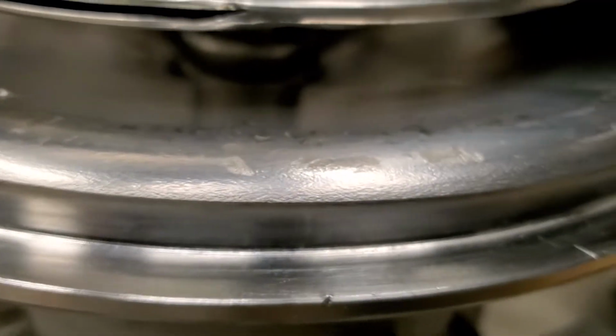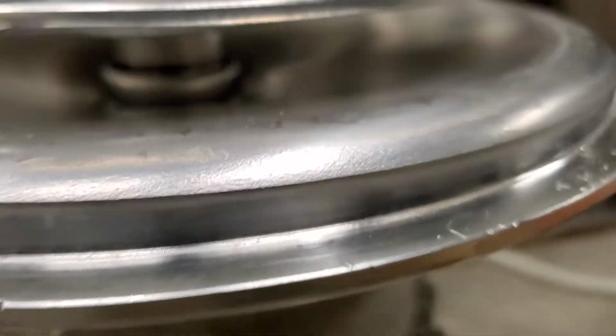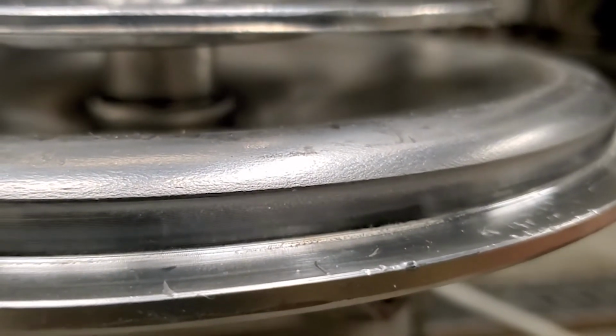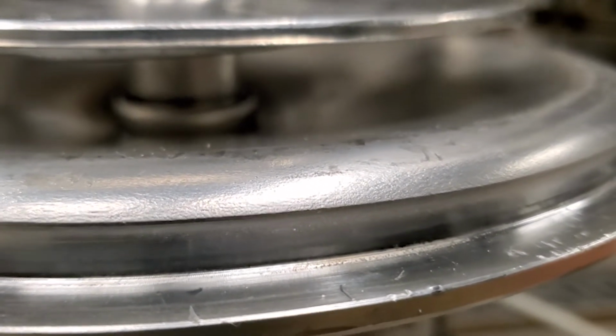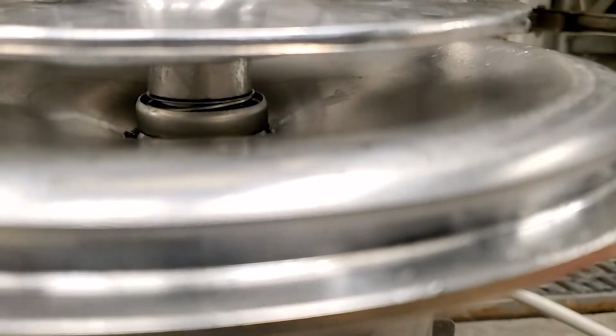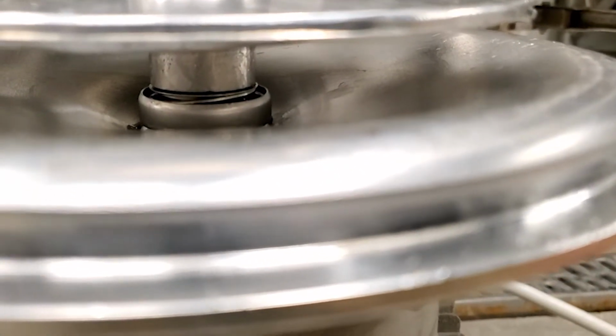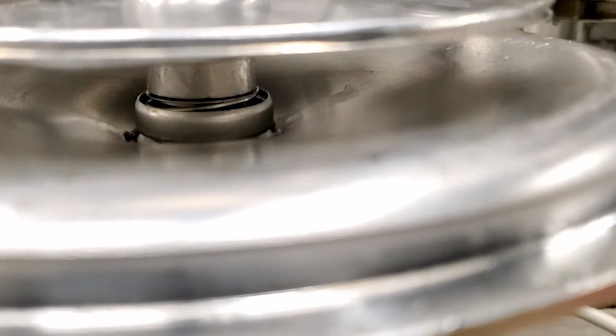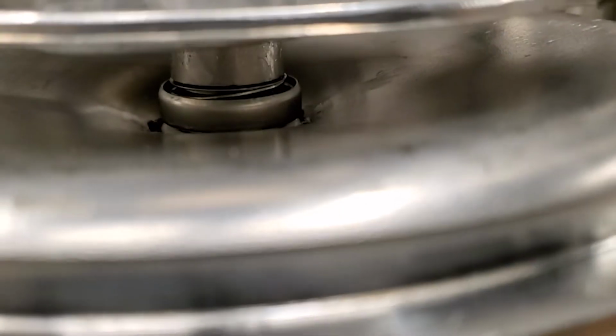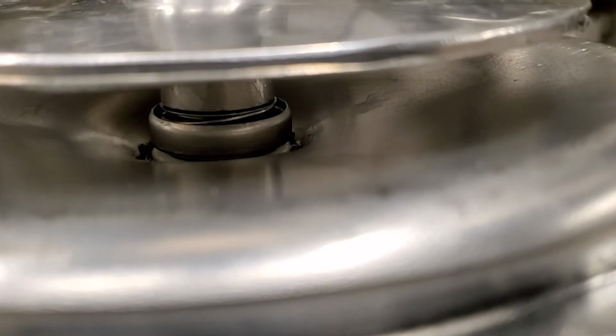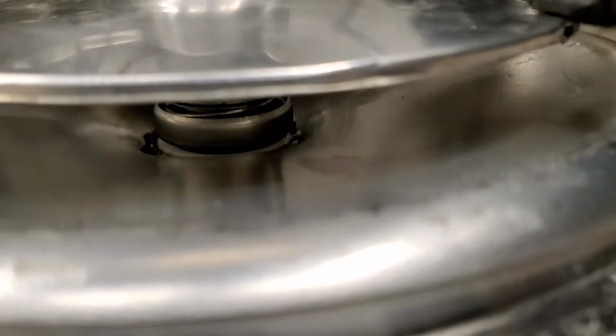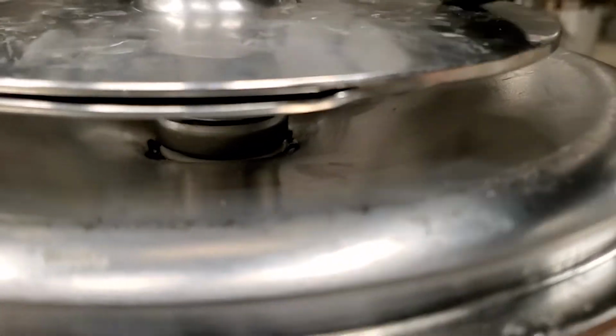I'm going to show you, see if we can catch a glimpse of how close we are. Yeah, you can see inside here that the backside of the impeller has compressed the pump seal. Looking pretty good in there, that's fantastic, exactly what you want it to look like. We're going to spin it a little bit so you can see it inside there. Beautiful, that's looking real good, that's what we want to see.